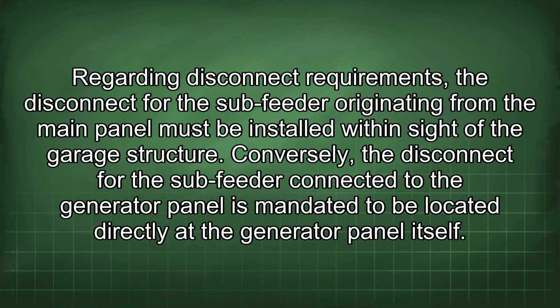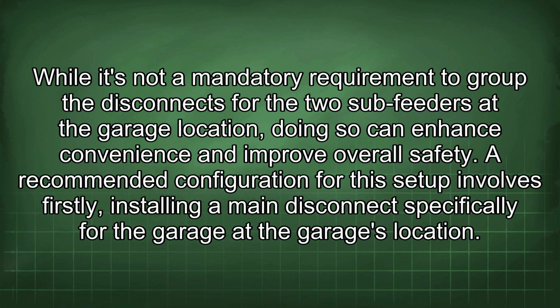Regarding disconnect requirements, the disconnect for the sub-feeder originating from the main panel must be installed within sight of the garage structure. Conversely, the disconnect for the sub-feeder connected to the generator panel is mandated to be located directly at the generator panel itself. While it's not a mandatory requirement to group the disconnects for the two sub-feeders at the garage location, doing so can enhance convenience and improve overall safety.